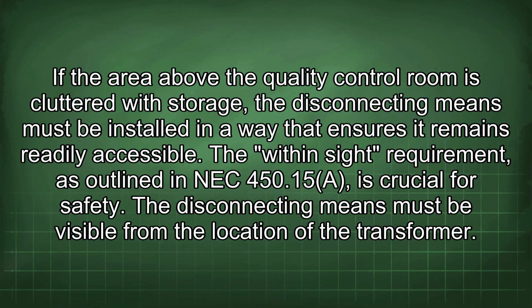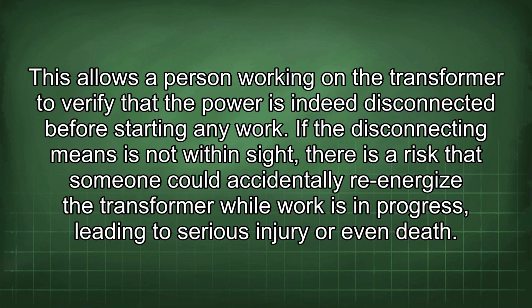The within-sight requirement, as outlined in NEC 450.15(a), is crucial for safety. The disconnecting means must be visible from the location of the transformer. This allows a person working on the transformer to verify that the power is indeed disconnected before starting any work. If the disconnecting means is not within sight, there is a risk that someone could accidentally re-energize the transformer while work is in progress, leading to serious injury or even death.